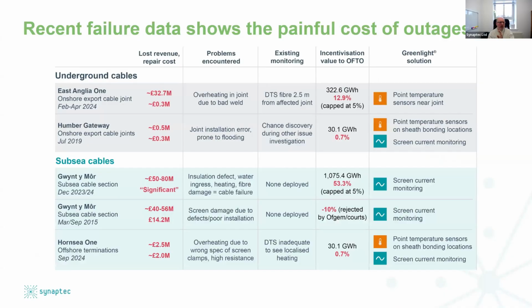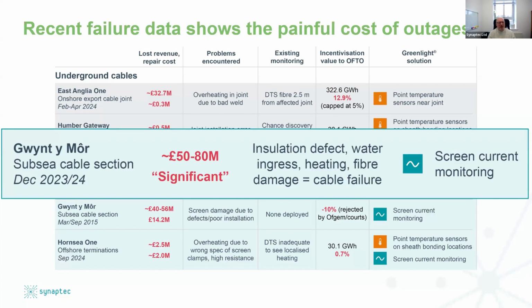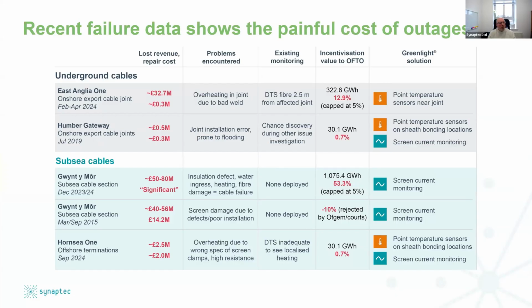So that's what we do. This chart I'll leave behind, but if I pick one out that I mentioned at the start here, was probably the most famous sort of poster child for cable failures, up to 80 million pound exposure. And interestingly enough, if you look at this chart, of all the recent ones that we spotted here in the UK, we're based in the UK, so of course I'm biased when I look at my numbers, whether it's underground or subsea cables, all of them were costing millions to fix, and all of them could have been seen in advance if Green Light were deployed on that circuit by looking at a combination of what's happening with phase current and its relationship to screen current, and also its relationship to the point temperature measurements of the terminations.